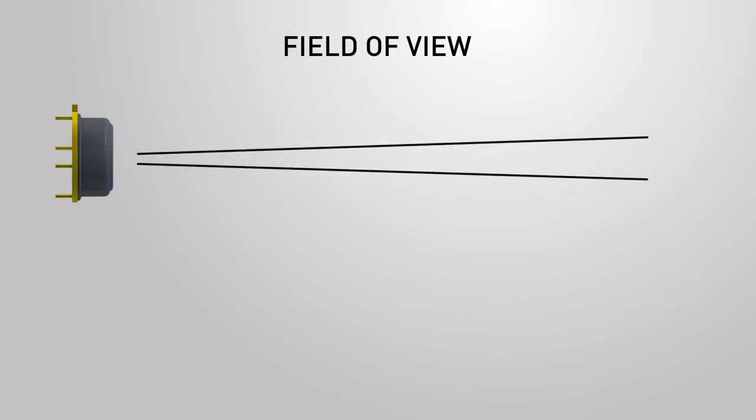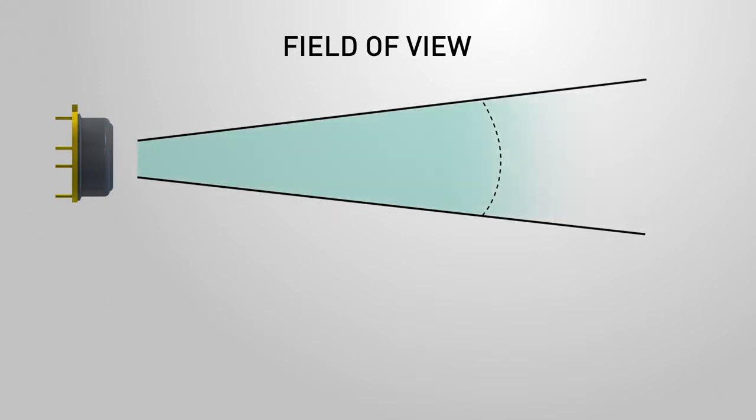The field of view of a sensor is determined by the angle in which the sensor is sensitive to thermal radiation. This means that the sensor will detect all objects in the field of view. The sensor returns the average of all objects in the field of view.